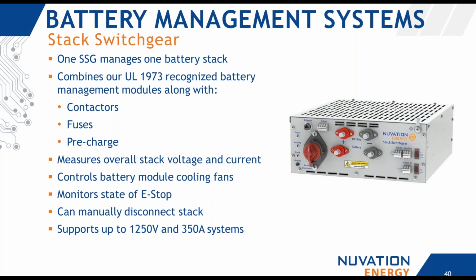So hunting around for the correct contactor or correct fuse is a task that you wouldn't have to do with our stack switchgear. It's going to be measuring your overall stack voltage and currents. It's controlling the cooling fans or integrating with your e-stop circuit. You can manually disconnect the stack for servicing through the service disconnect switch. And as far as the high-end version, that's 1250 volts and up to 350 amps. So pretty substantial size.